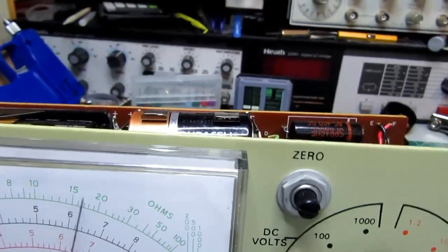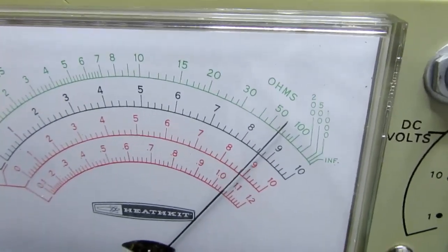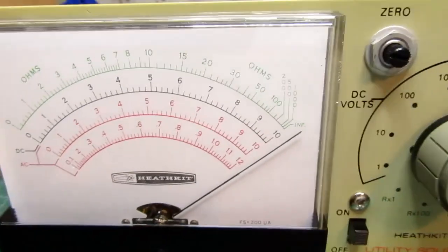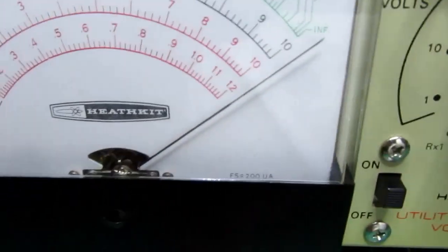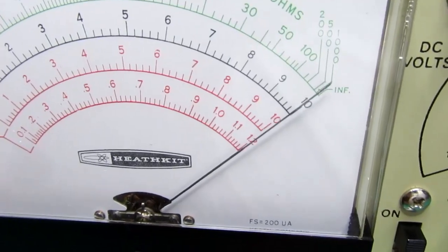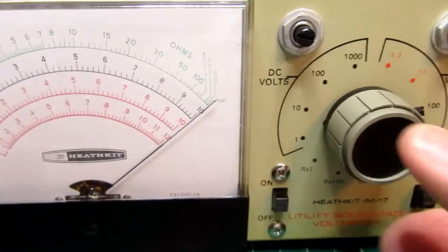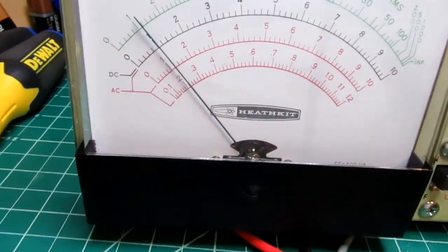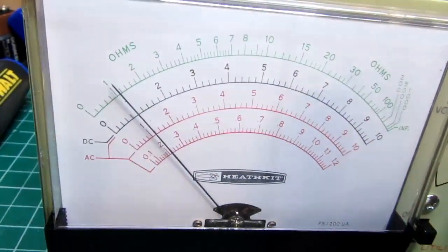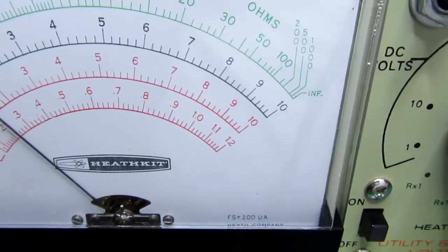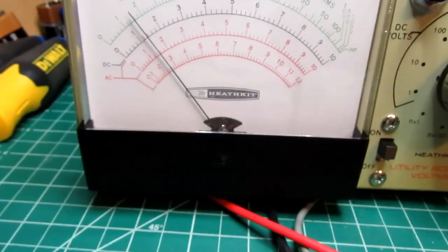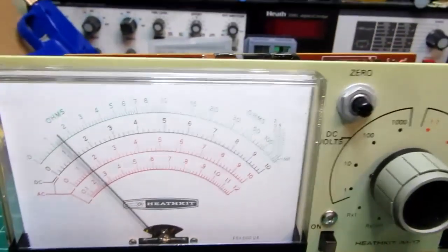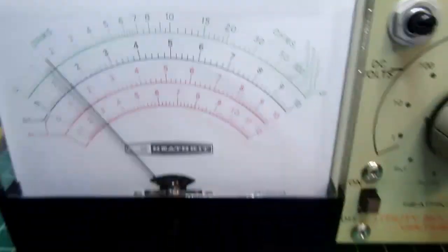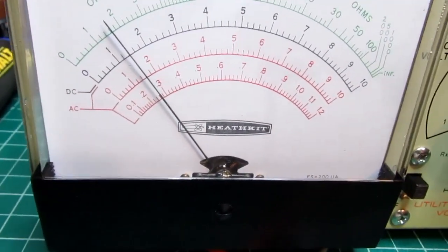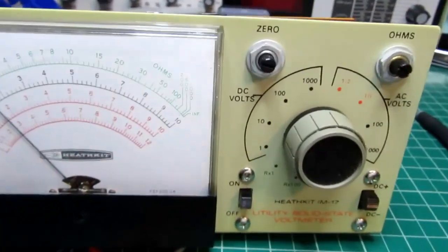And if I go to around about 100 volts, it's slightly over range there. The Variac meter is not very precise. And if I want to read higher, I can go up to the 1000 volt range, and it's reading about 100 on the 1000 volt range. So if I go up to about 120 volts ish, well, it's reading low here because again the Variac's not very accurate. That's more like it. Anyway, so the AC volts function is working.